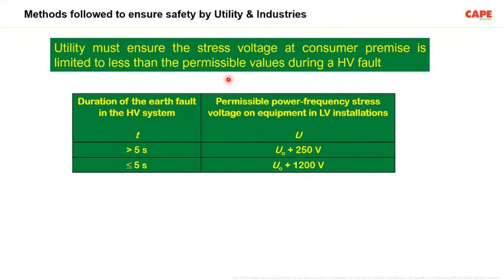With respect to utility companies, one of the responsibilities of the utility, the first responsibility, which I told you, is that in case of any fault on the consumer premises, the incoming fuse must disconnect within the time specified in the standard. Number two, the utility should also take care of faults on the high voltage system. On the left-hand side, what I am showing is the duration of earth fault in the high voltage system. Of course, with an 11 kV transformer, in case of a fault on the 11 kV side, a temporary overvoltage will appear on the 230 volt side.